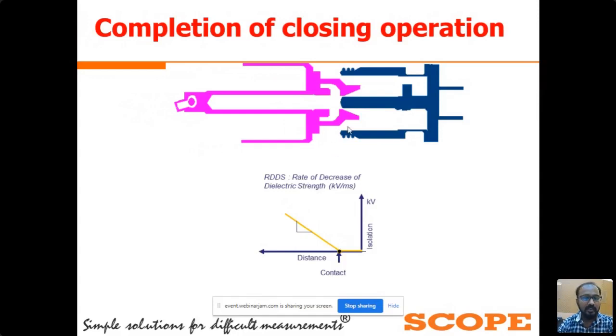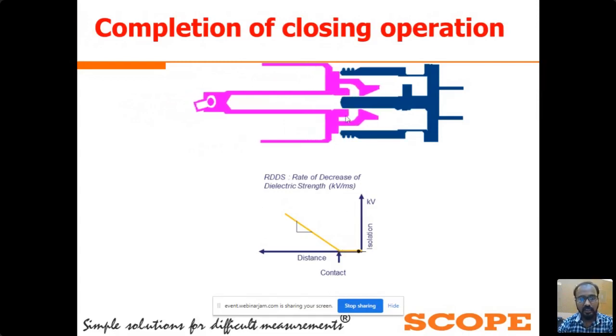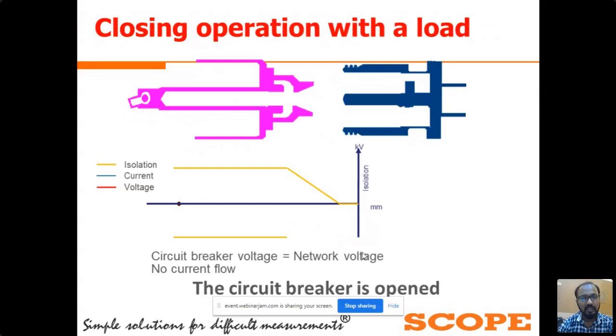The rate of decrease of dielectric strength is an important parameter during the commissioning of a control switching device. Here you can see, once the CB contacts are physically in touch with each other, the dielectric strength between the contacts is near to zero. Now we will see the closing operation of the circuit breaker with the load.